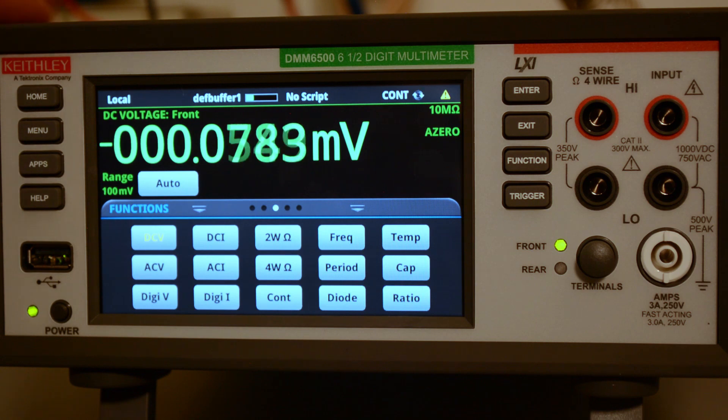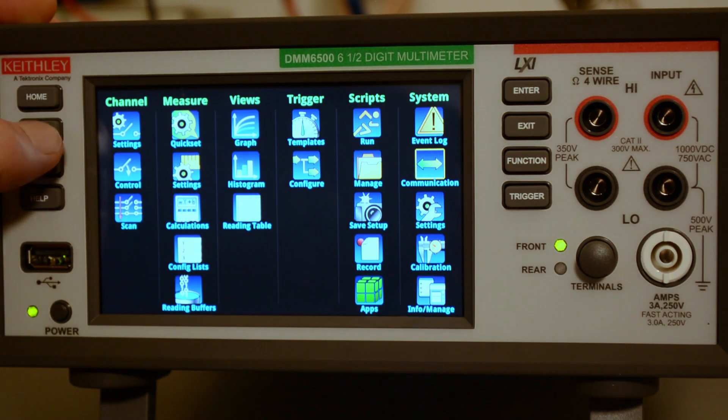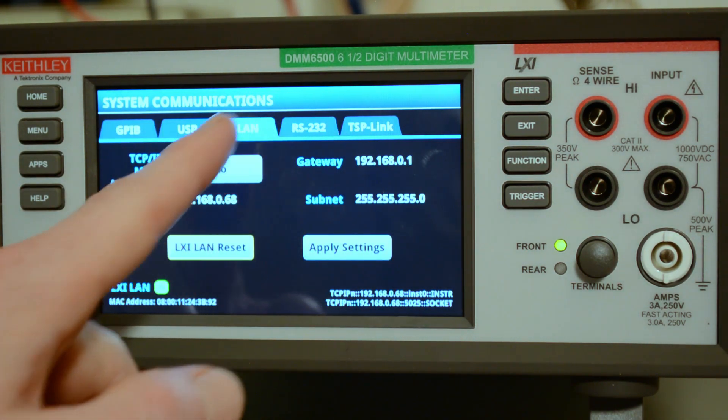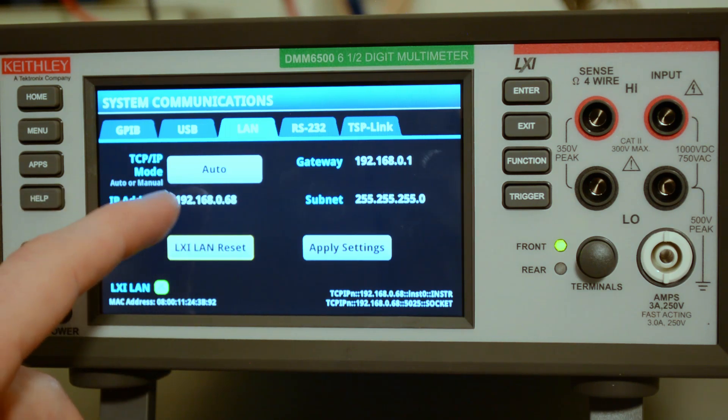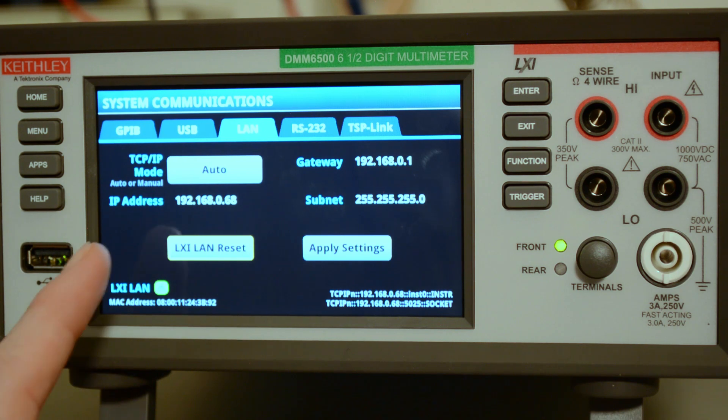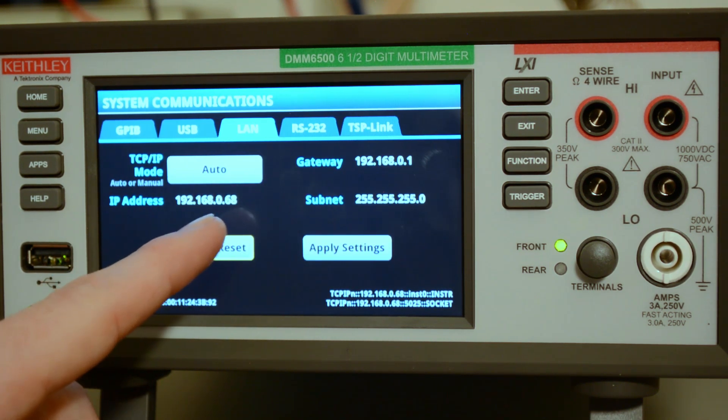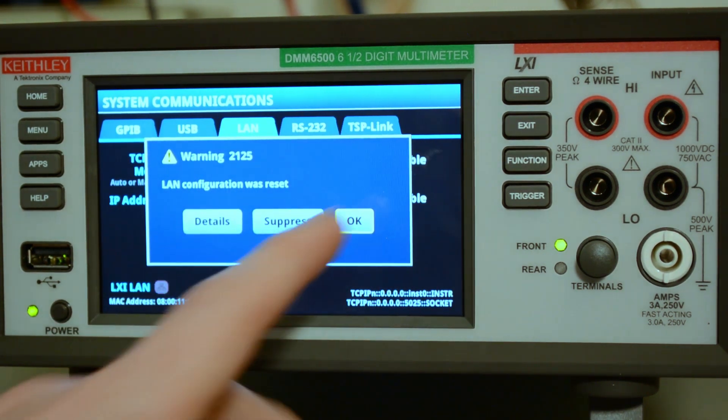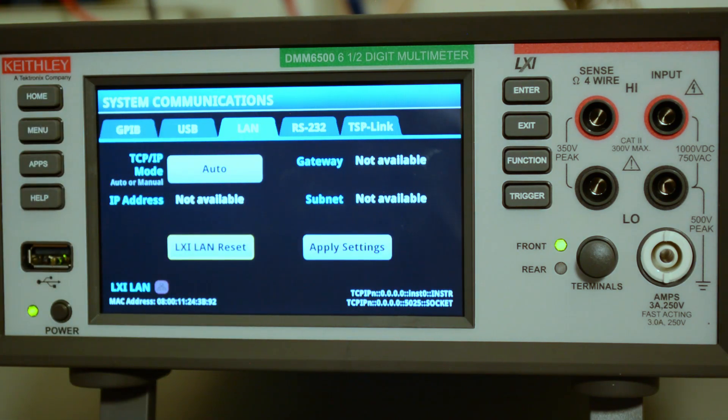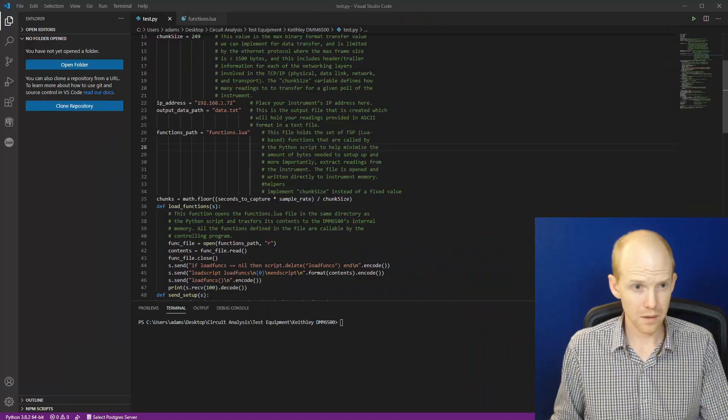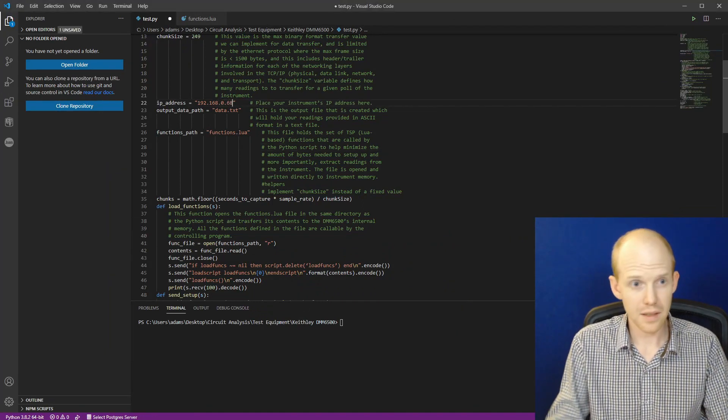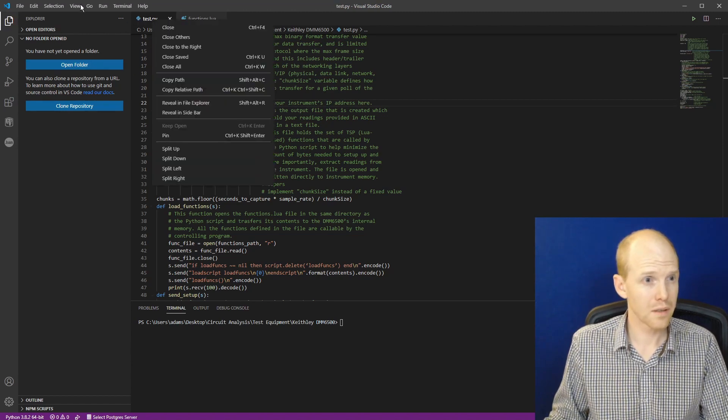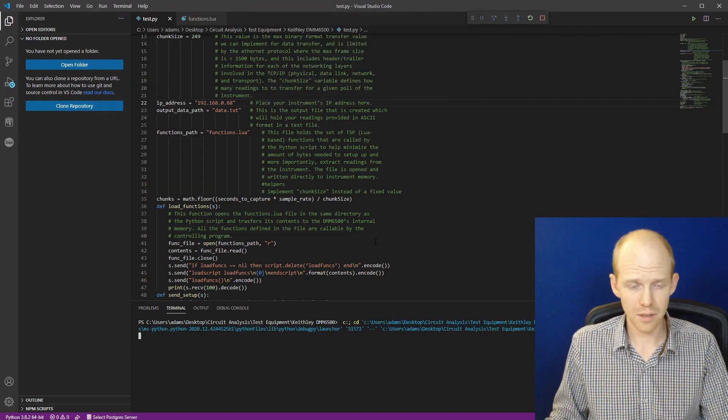So back at the meter, to find the IP address, we go to menu, and communications, and then LAN tab. So here it is right here. So mine's 192.168.0.68. I did just try this, and it was a little weird, and it didn't work. So what I did was I hit LAN reset here. And that reset everything. And then it changed the address. I guess I got a new one. And it worked after that. So we'll go back to the computer. And now I'll change this to 0.68. Save that. And we'll run the script.